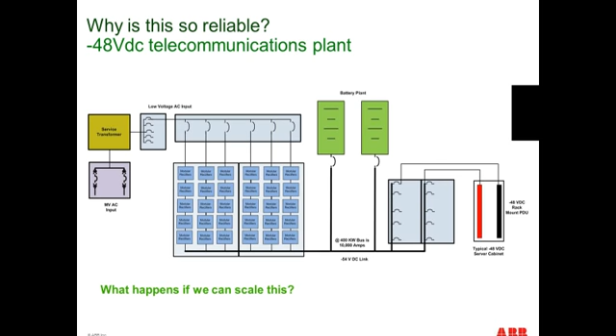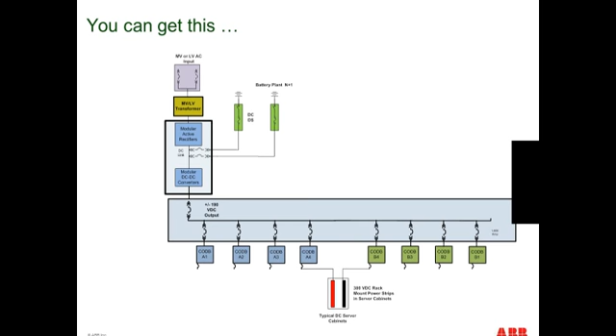If you took a 48-volt telco system and kept all its attributes, you'd get something like this: a medium voltage service entrance transformer with that same modular rectifier array, float charging, a slightly higher voltage bus, and the same style of modular, scalable rectifiers. If you'd like N+1 or 2N redundancy, you simply rack an independently controlled rectifier or DC-to-DC converter into the array to gain similar levels of reliability as that telco system.